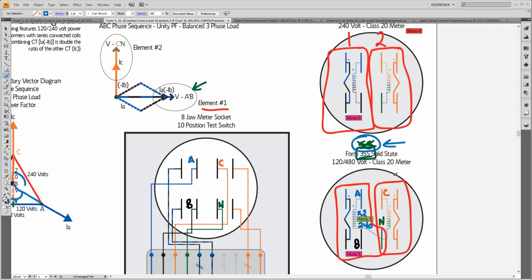And so if the load was really balanced, I'd be off by what would be this voltage being 120 and this voltage being 208, so I get half of the torque of my meter here, and then half of what I should get out of here, instead of getting what I would get if I had the right meter, the 35S, that did this math inside of the meter. So that was the 35S. Like I said, we changed a lot of those meters out. There was just a process that you had the meter, you'd have a list of where the wrong ones were, and you'd go out and get the wrong one out and put the right one in. But there was at least one that I was aware of that slid through the cracks there in Cedar City.